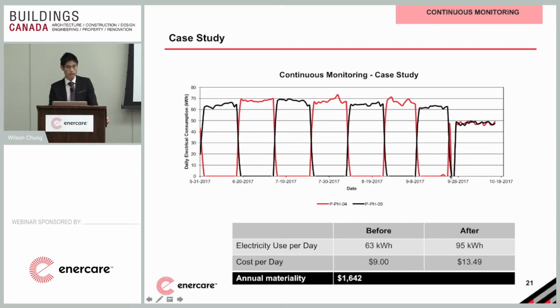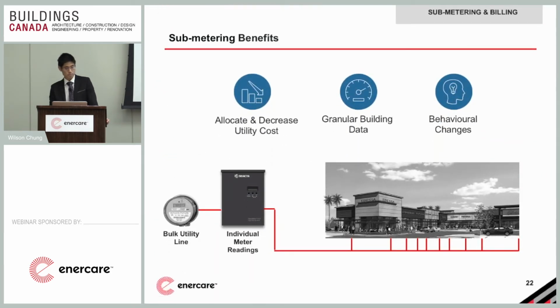Suddenly, in this period, everything went down—an anomaly happened. Maintenance people went in and fixed it, and now you have this profile going forward. What happened is that instead of restoring the duty-and-backup pump controls, they made both pumps operate at the same time. What does this mean? Before, in the as-designed situation, you're operating at around 63 kilowatt-hours a day, $9 a day. After this, you're operating at 95 kilowatt-hours a day, $13.50. Over the course of a year, that's a $1,600 difference. So if you didn't monitor this data and catch it, letting it run over time, you're at a loss—and that's one of the values.